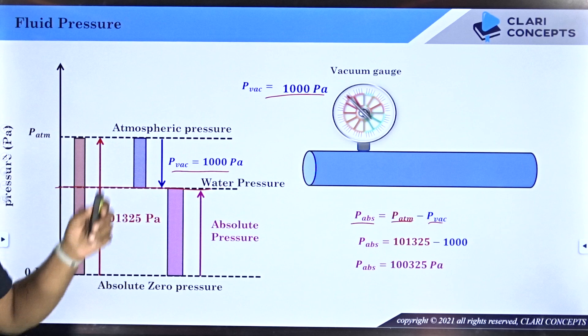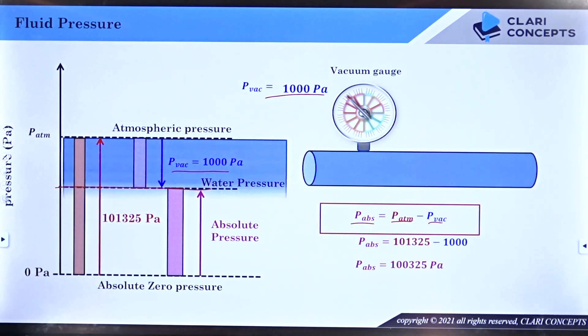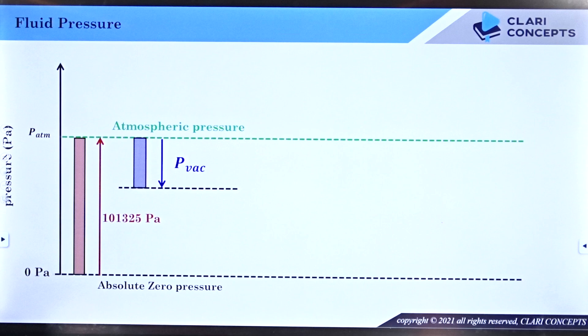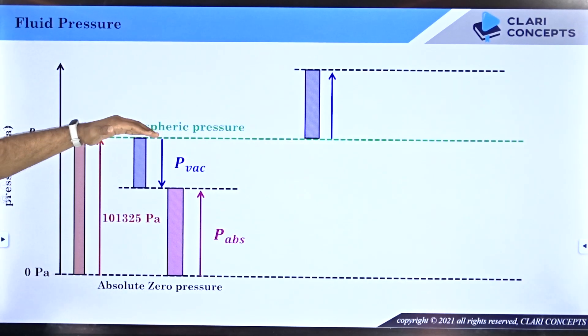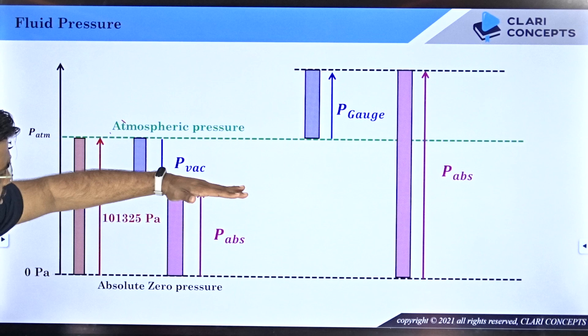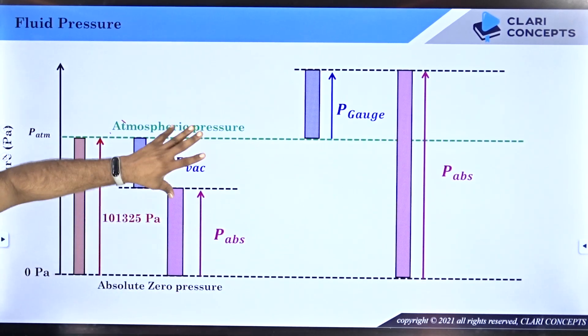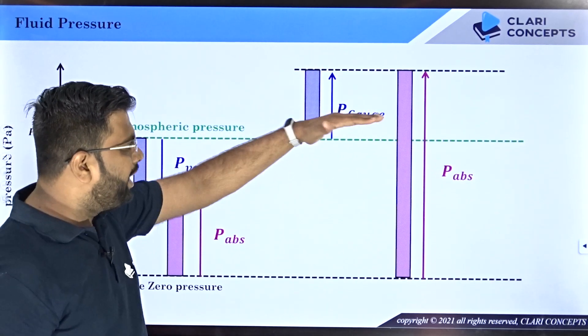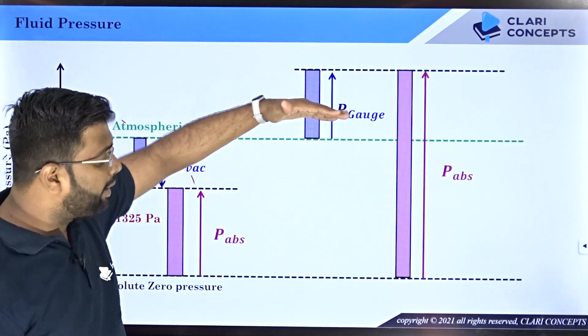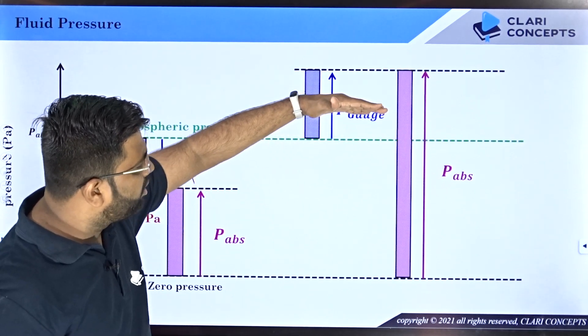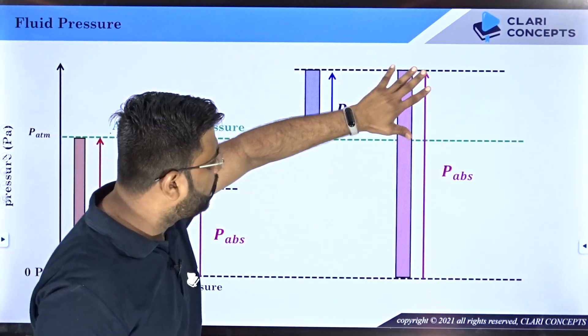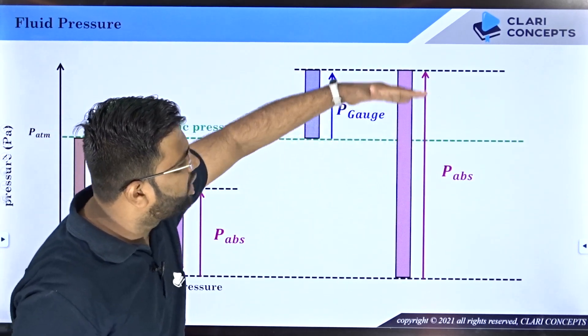That is why vacuum and gauge pressure came into existence. Vacuum pressures are normally used to measure pressure below atmospheric pressures. Now this is the final chart — the atmospheric pressure line is here. Vacuum pressure is always measured below atmosphere, and if you want the absolute pressure of that, you subtract vacuum pressure from atmospheric. Gauge pressure is measured above the atmospheric pressure line, and if you want the absolute value, you add atmospheric value with the gauge pressure.